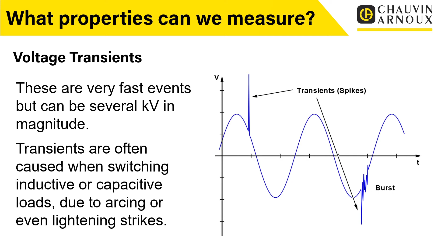And a lot of the time this is due to switching on and off capacitive or inductive loads. It could be due to arcing. You can imagine maybe using welding equipment, or there's an arc in a switch, maybe a switching contact or a relay contact has become corroded, and you're actually getting that little bit of arcing in there that could be causing this. Or even environmental effects such as local lightning strikes can cause this sort of thing to happen. So again, one of the things we are looking for when we do power quality measurement is transients, but these are very, very fast events. So we really need to have our instruments set up to be able to capture these things, because they do happen, sometimes in the case of microseconds. So we do need to really be set up to capture these when they happen.